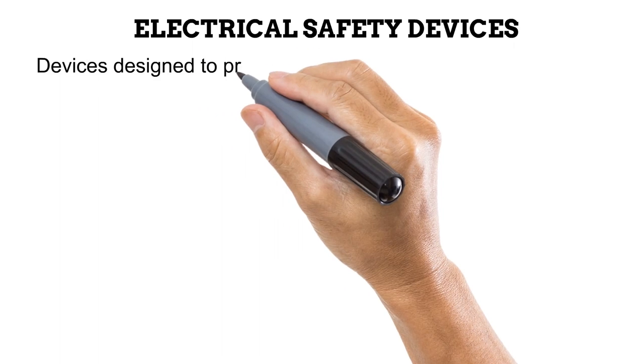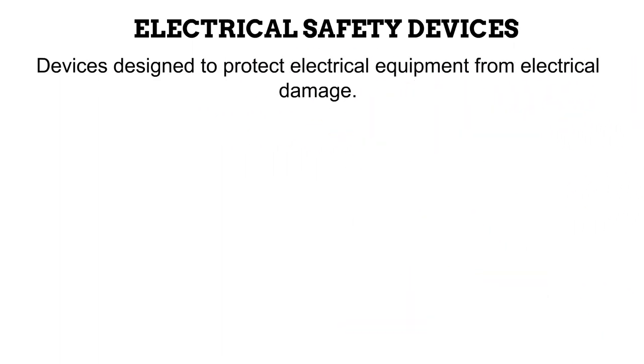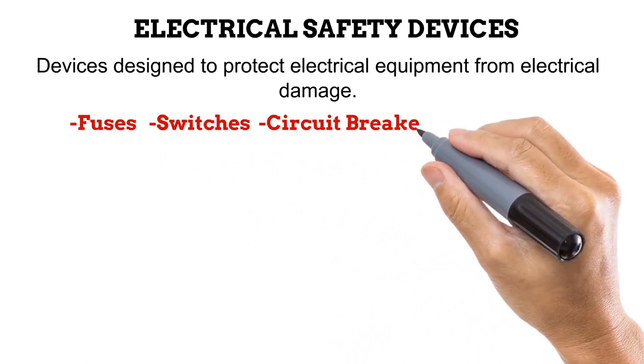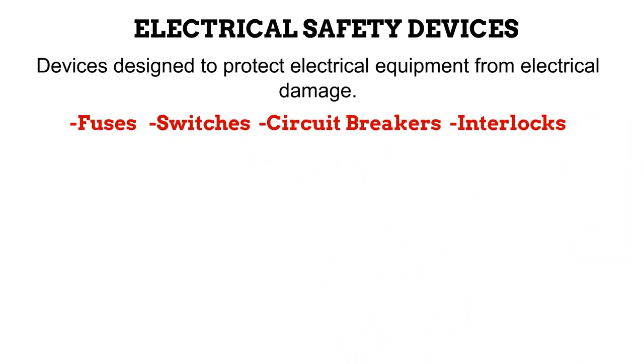Over the last four videos, we have learned about how electricity is generated and passed into the X-ray unit for use. There are times when this electrical supply could be problematic. In cases of electrical overloads and power surges, electricity could damage the equipment it supplies. Devices known as electrical safety devices are in place to reduce this. Common electrical safety devices in radiography include fuses, switches, circuit breakers, and interlocks.